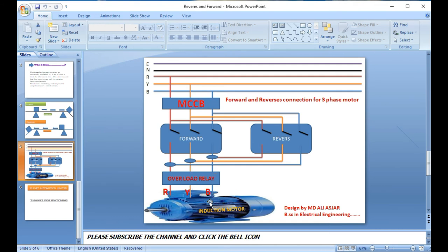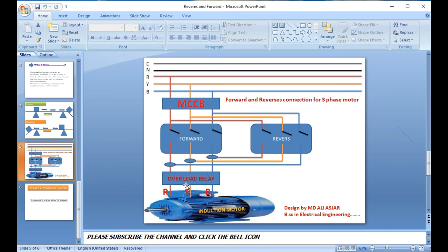The overload relay is also included in this system. It is normally closed (NC) during normal operation. When the motor is running under normal load, the NC contact keeps the circuit energized. If an overload fault occurs, the overload relay trips — the NC contact opens and becomes NO (normally open), cutting power to the motor and protecting it. The MCCB also protects devices from voltage faults, current faults, and any kind of systematic fault, providing emergency stop capability.